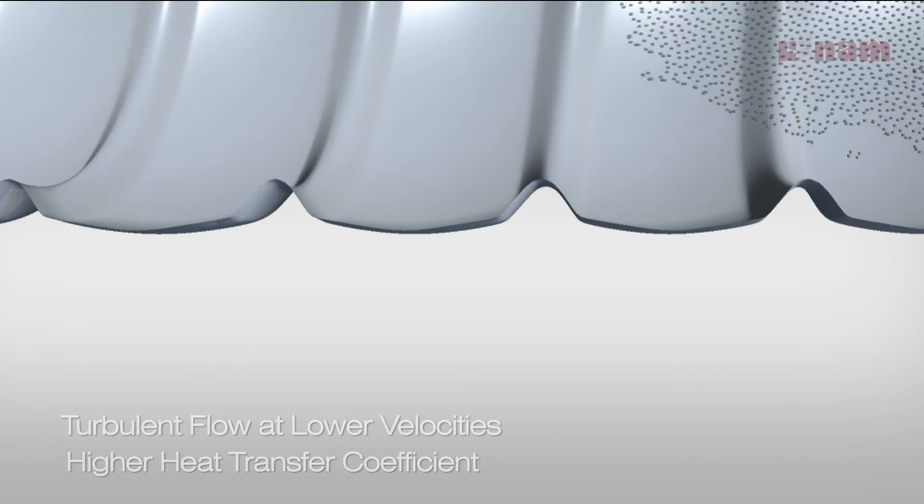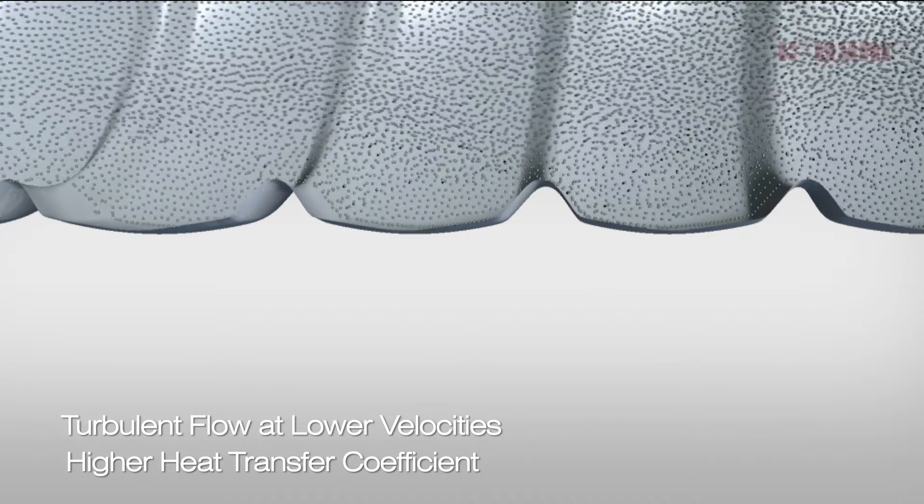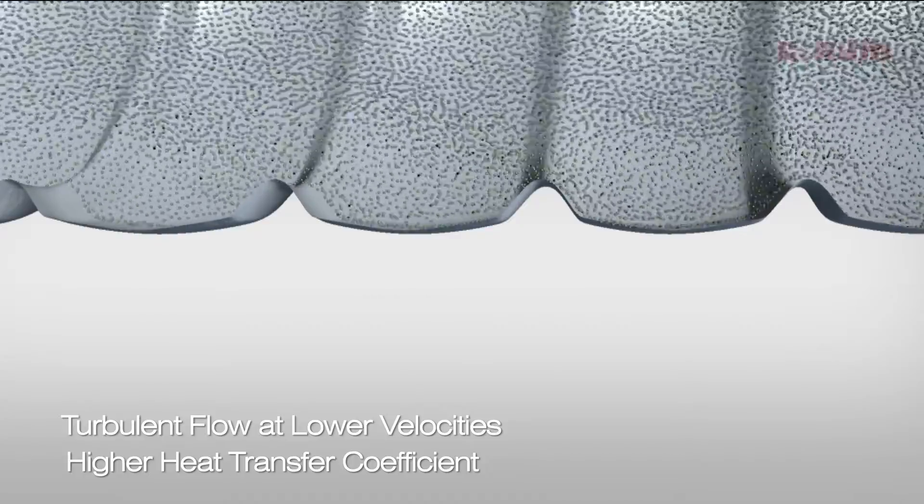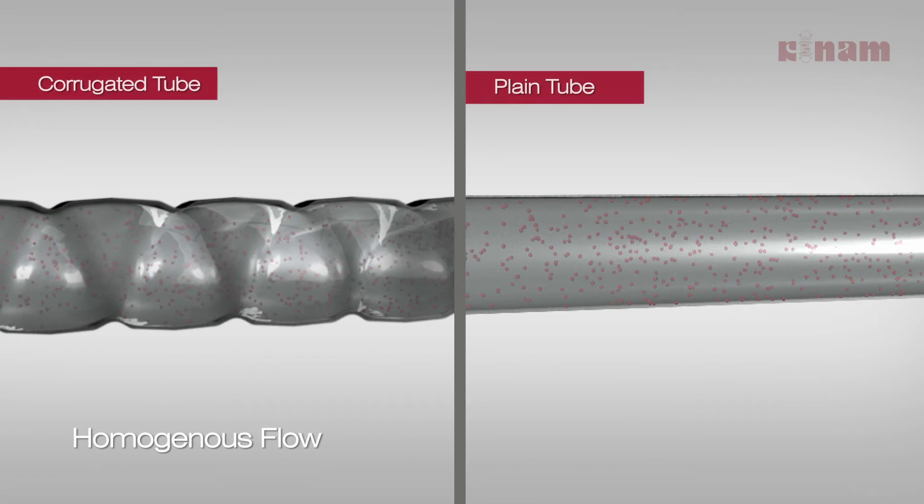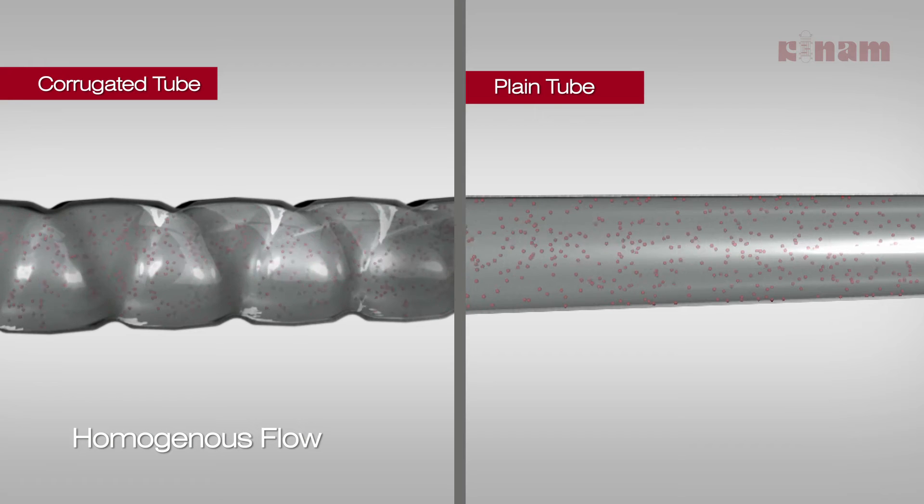Thus, corrugated tubes induce turbulence in the fluid, even at lower velocity at the peripheral layer, which results in higher heat transfer coefficient. The two-regime flow enables thorough mixing of the fluid, ensuring homogenous fluid mass rather than layered flow pattern.